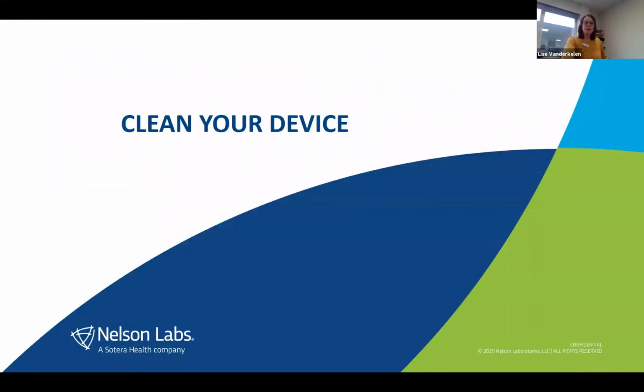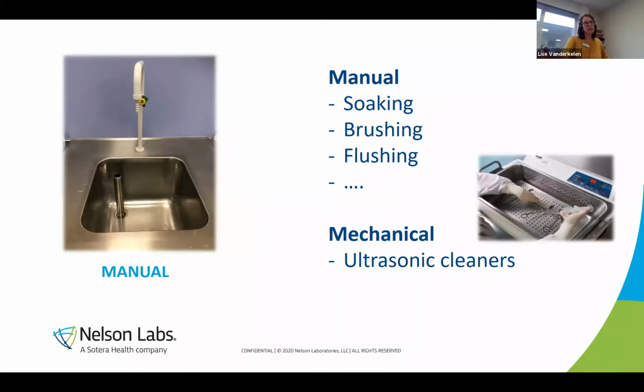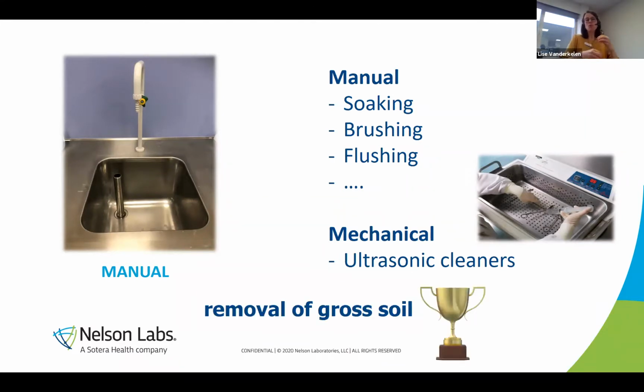Then you're going to clean your device. There are two main ways of cleaning your device. You have manual cleaning. It's really like standing at the sink, soaking, brushing, flushing. Sometimes a mechanical step is included with ultrasonic cleaners. And here I must say that removal of gross soil is essential before you use the mechanical or the ultrasonic cleaner, because otherwise your water will be easily saturated already with the gross soil and it will be very hard to clean and your validation probably will fail. But in real life, it's also not good practice.